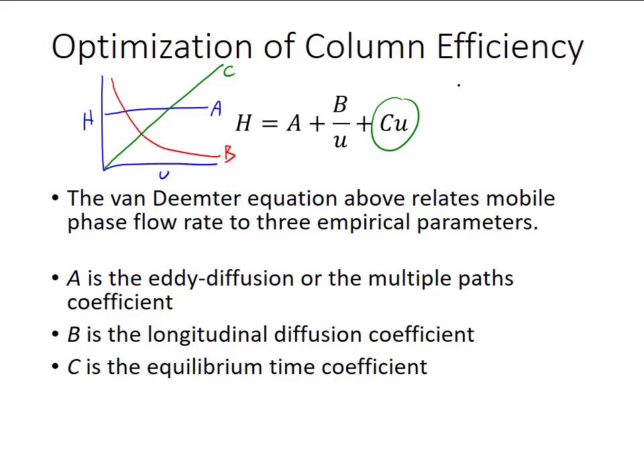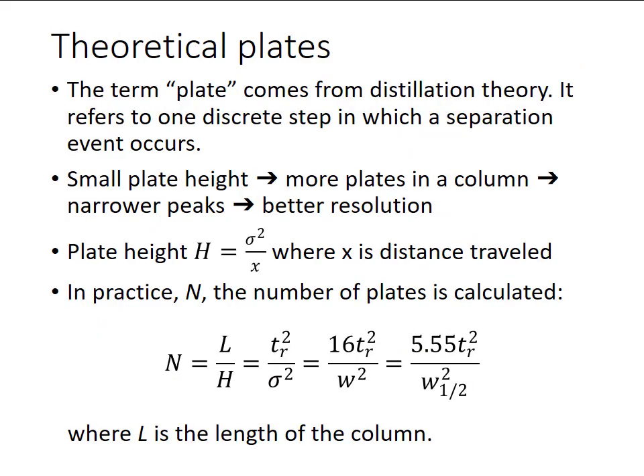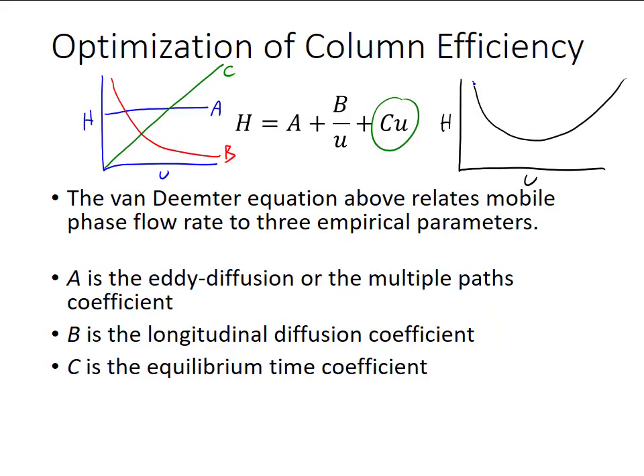Together, these three parameters contribute to a Van Deemter plot that looks like a curve with a minimum. In practice, we measure the height of theoretical plates from the retention time, width at half height, and column length at different flow rates, plot the resulting curve, and use the minimum from this analysis as our flow rate for optimal column efficiency.